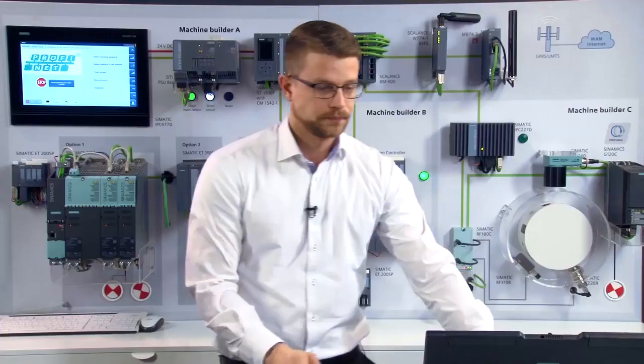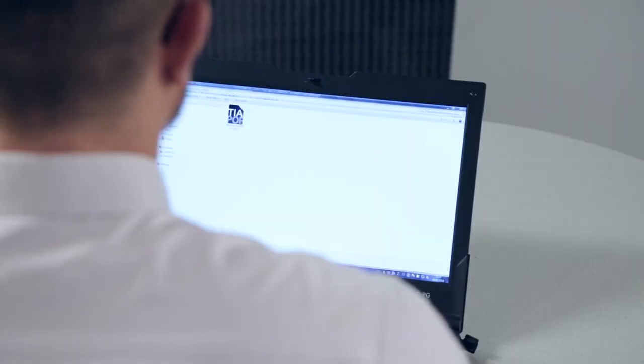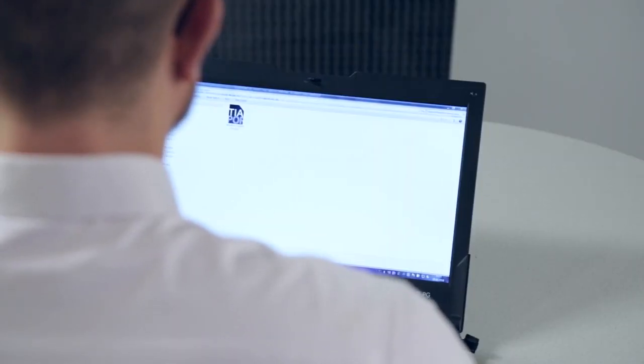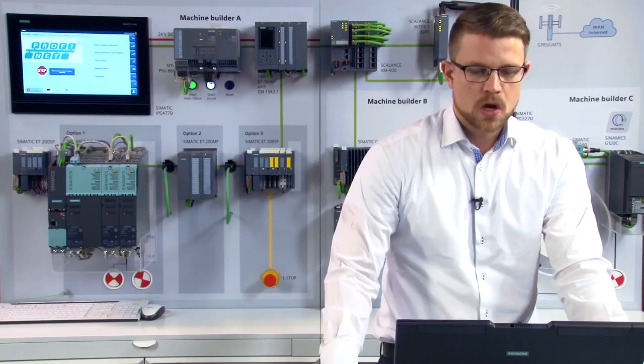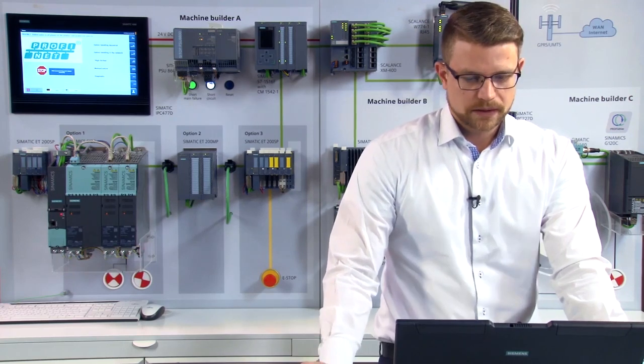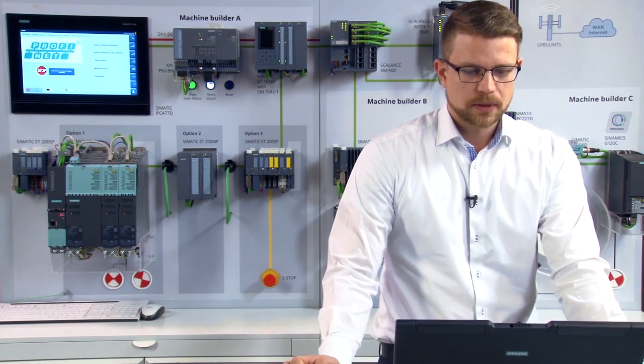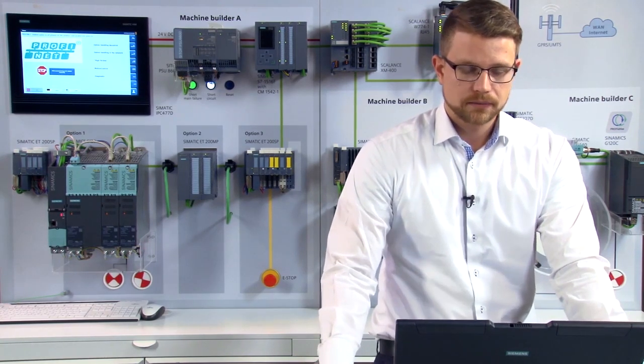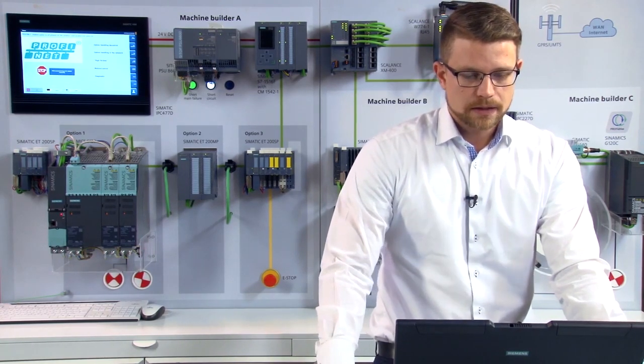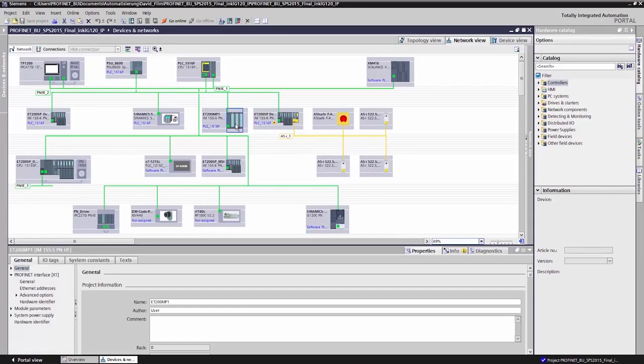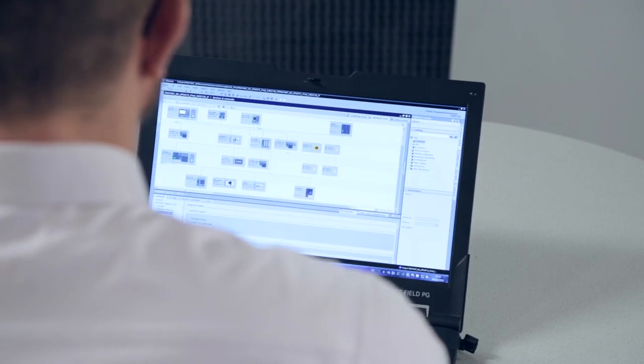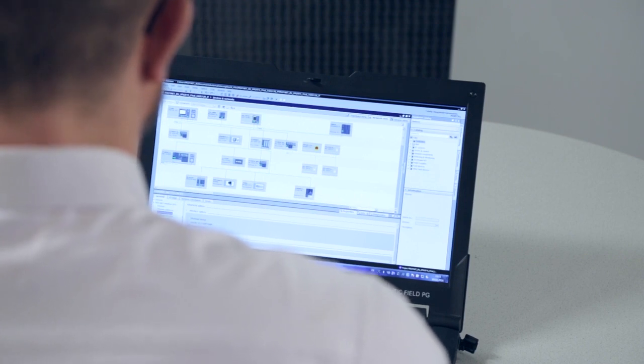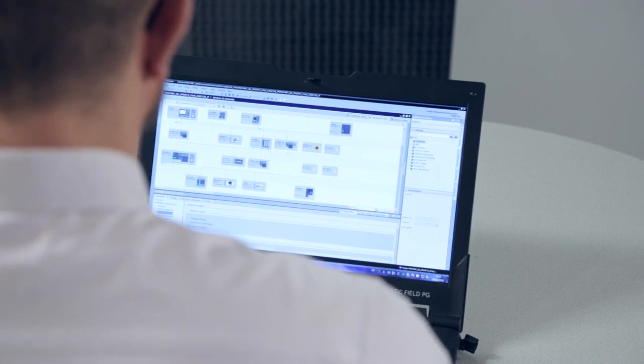Let's take a quick look at the actual project. Select a single project in the full configuration will suffice. And now I choose the ET200MP as an optional device in this configuration. Under Advanced Settings, I see that optional I/O device has been selected. This informs the TIA portal that we consider the hardware configuration of the ET200MP as an option.